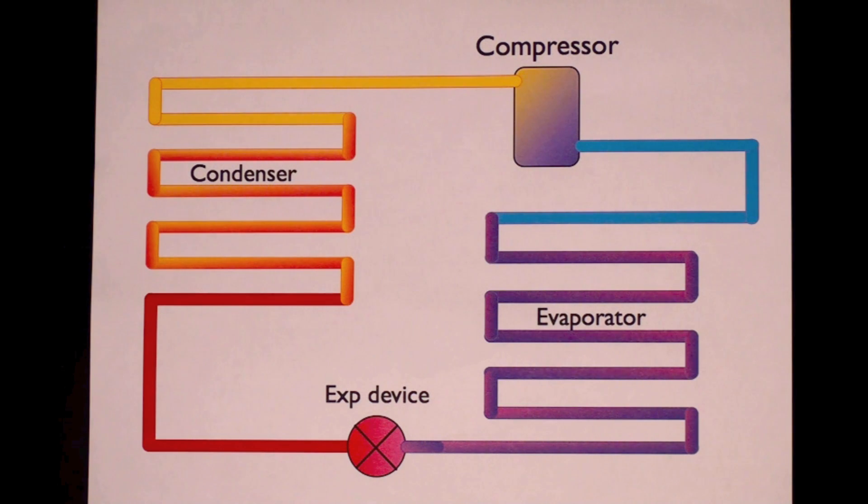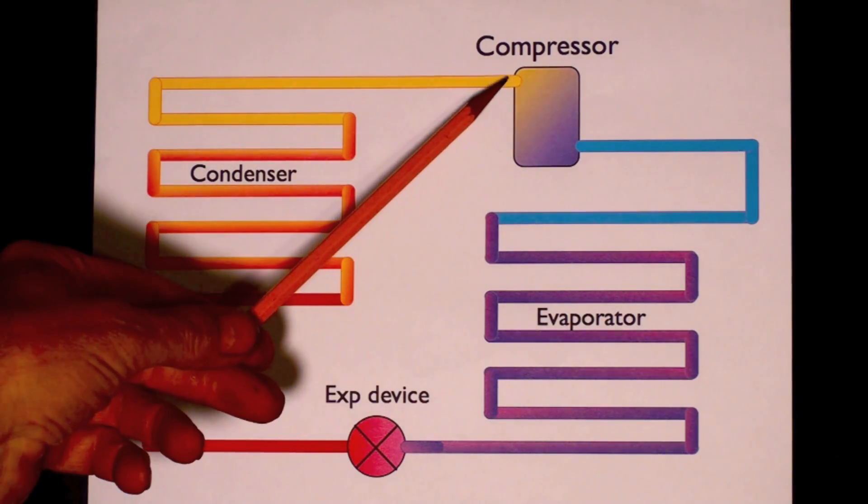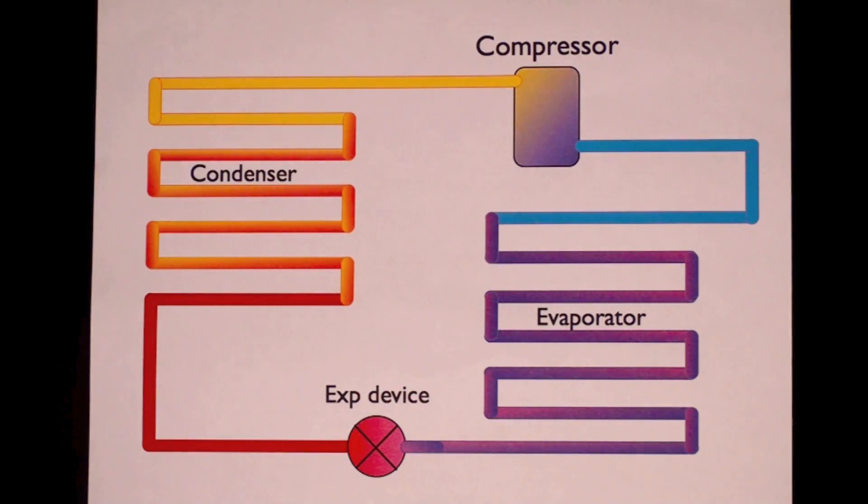So let's follow this refrigerant as it comes out of the compressor. Okay, now it's a high pressure gas. We call it highly superheated hot gas. It passes out of the compressor. It goes to the condenser. The top part of the condenser takes that high superheat off and drops its temperature. When it reaches past the first couple of runs in the condenser, it begins condensing.